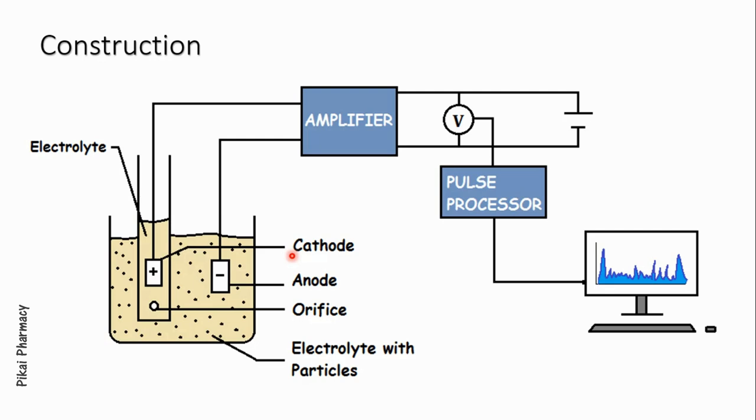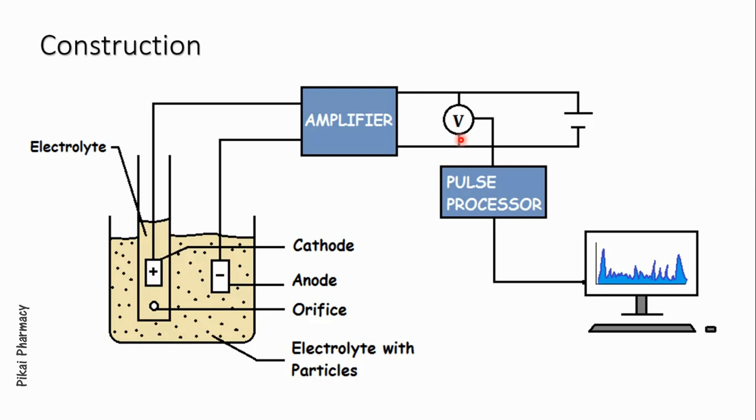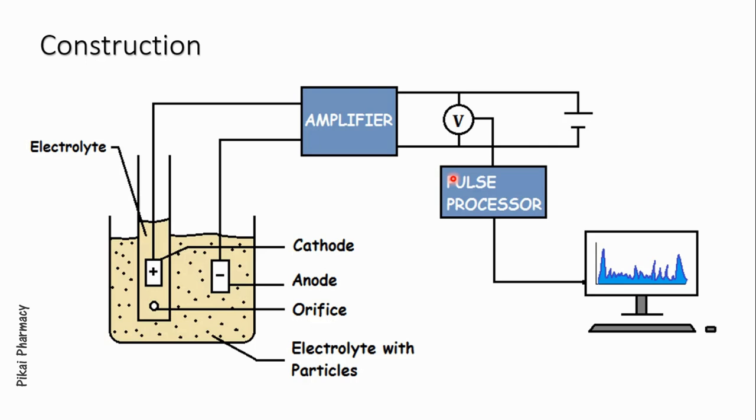The electrolytic solution inside the glass tube contains the cathode electrode and the outer electrolytic solution contains the anode electrode. This whole thing looks like a setup of an electrolytic cell, and yes it is, but there are some additions: there is an amplifier and a voltmeter attached to the circuit which is further connected to pulse processing units. Now let's discuss the principle of the Coulter counter.